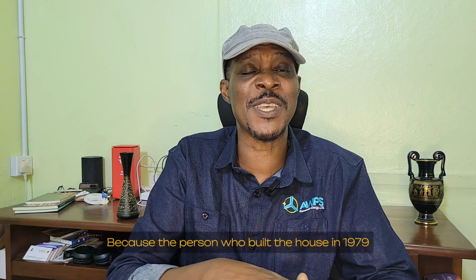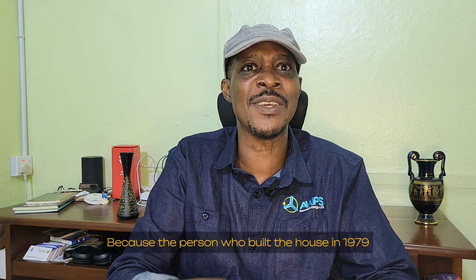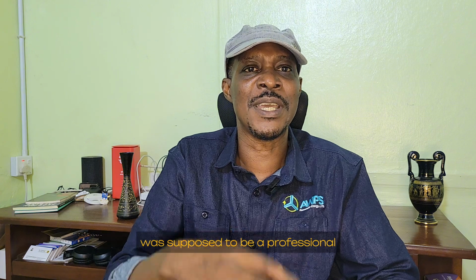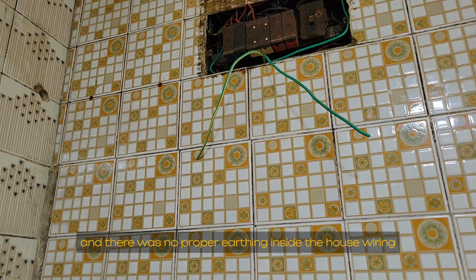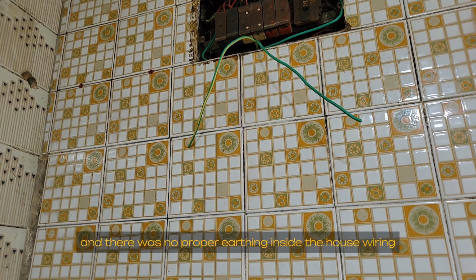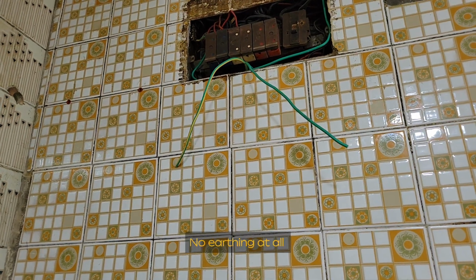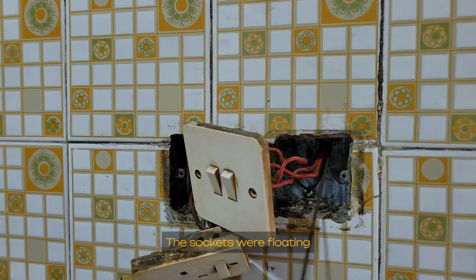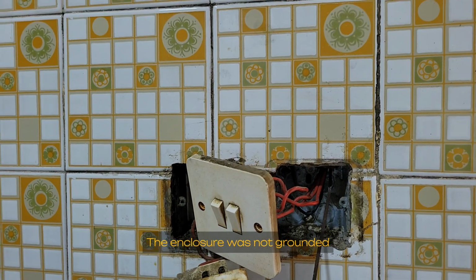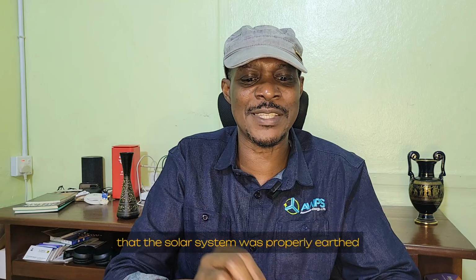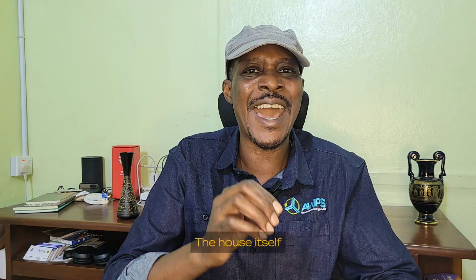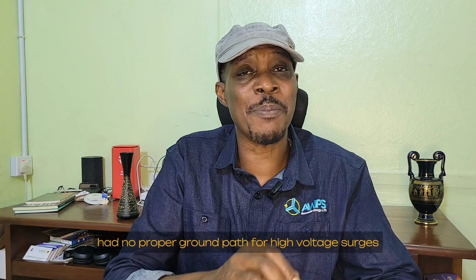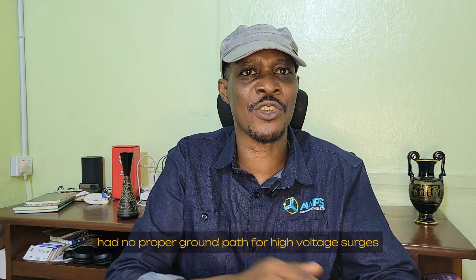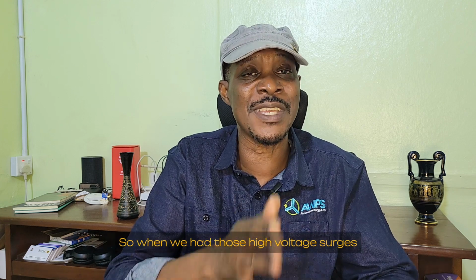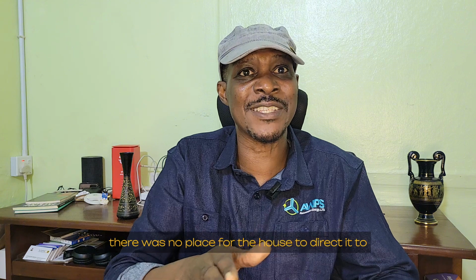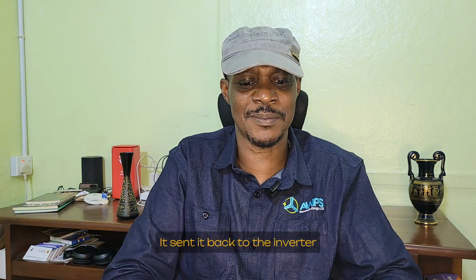Why was I shocked? Because the person who built the house in 1979 was supposed to be a professional, and there was no proper earthing inside the house wiring—none. No earthing at all. The sockets were floating. The enclosure was not grounded. It didn't matter that the solar system was properly earthed; the house itself had no proper ground path for high voltage surges. So when we had those high voltage surges, there was no place for the house to direct it to. It sent it back to the inverter.